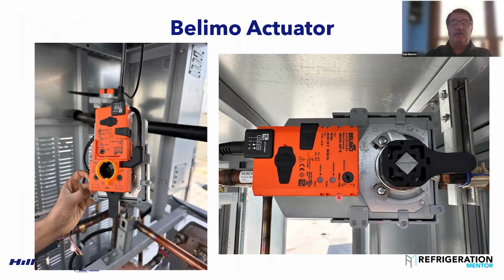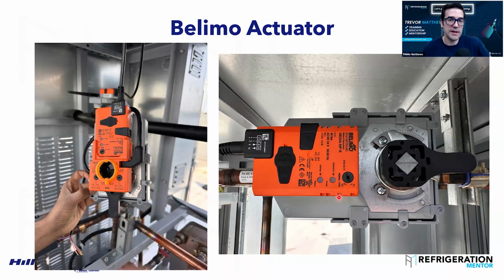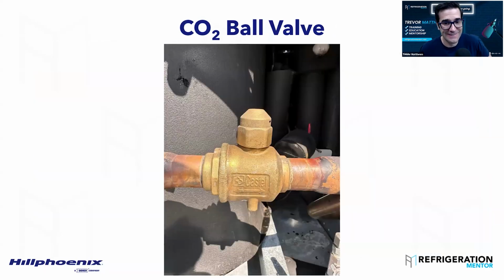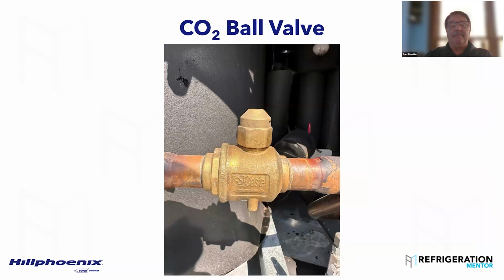Yeah. And what we ended up doing was putting a delay in this Belimo of 30 seconds to allow the other one to open before we allowed the hot gas to start flowing. And yeah, in CO2 systems, like any ball valve, you want everything to open and close slowly, even though everything works very fast.